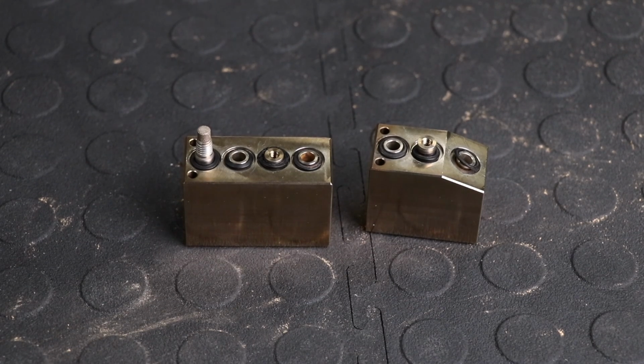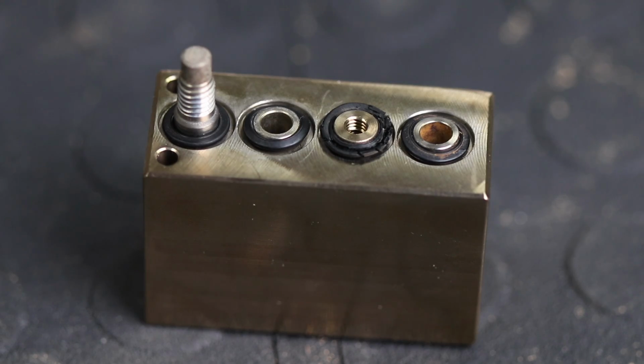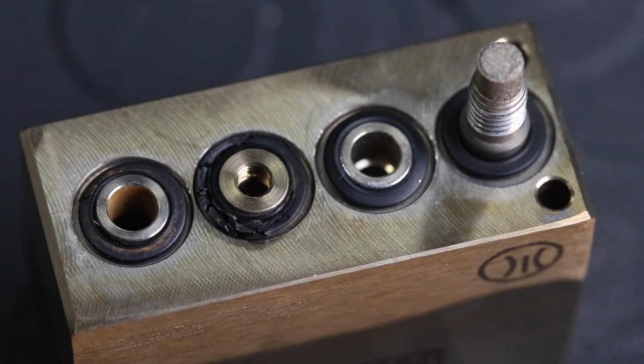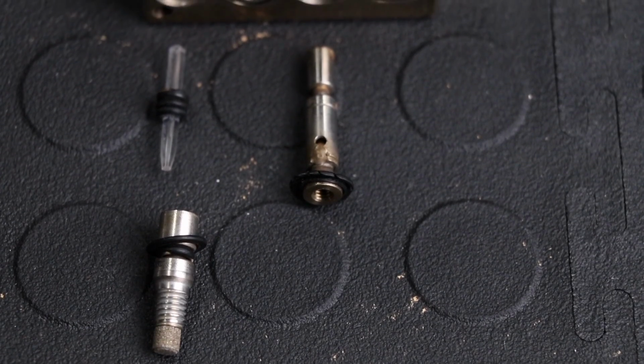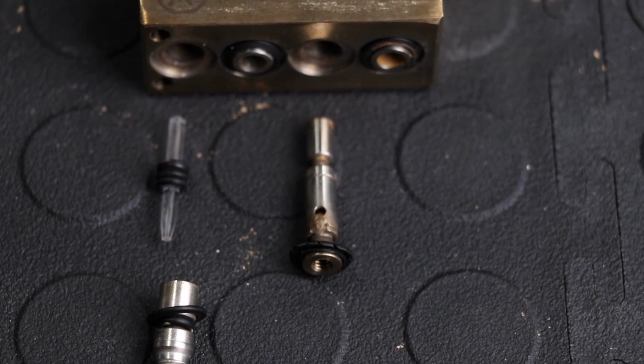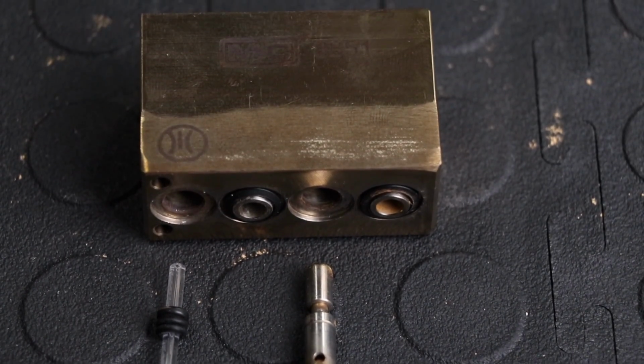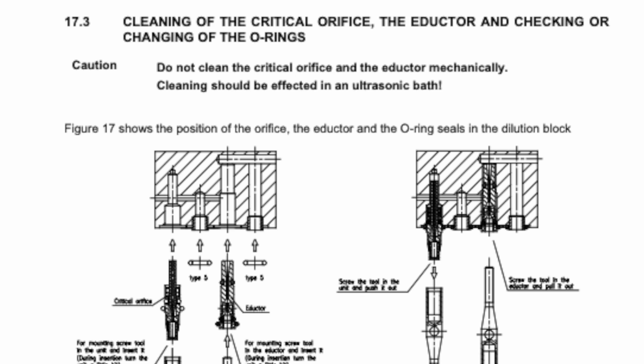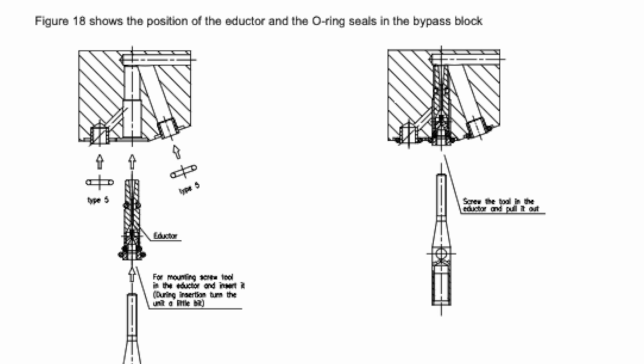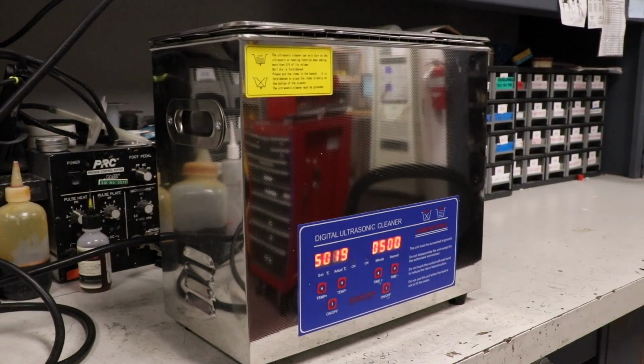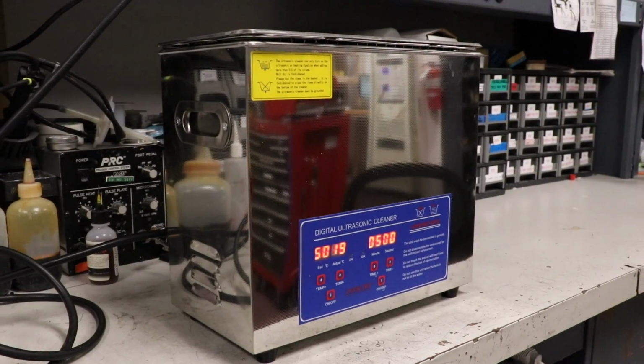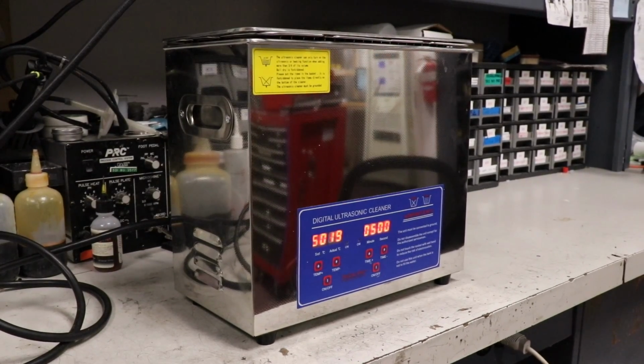Inspect the O-rings. If they are damaged or flattened, replace them. Use the provided tool to remove the critical orifice, eductor, and bypass eductor from the blocks. Refer to Chapter 17 in the user's manual for an exploded drawing of the equipment. Do not clean these pieces mechanically. Clean the orifice and the eductor in an ultrasonic bath.